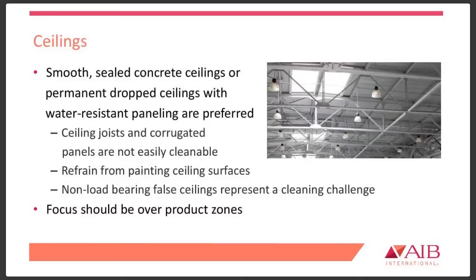Non-load-bearing false ceiling panels are also not recommended, as the voids are difficult to clean and inspect. When they're opened by personnel from below, any accumulated dust and debris can get dispersed into the production area. Furthermore, they're not always resealed properly, and any unprotected openings to the ceiling void can certainly be an issue.